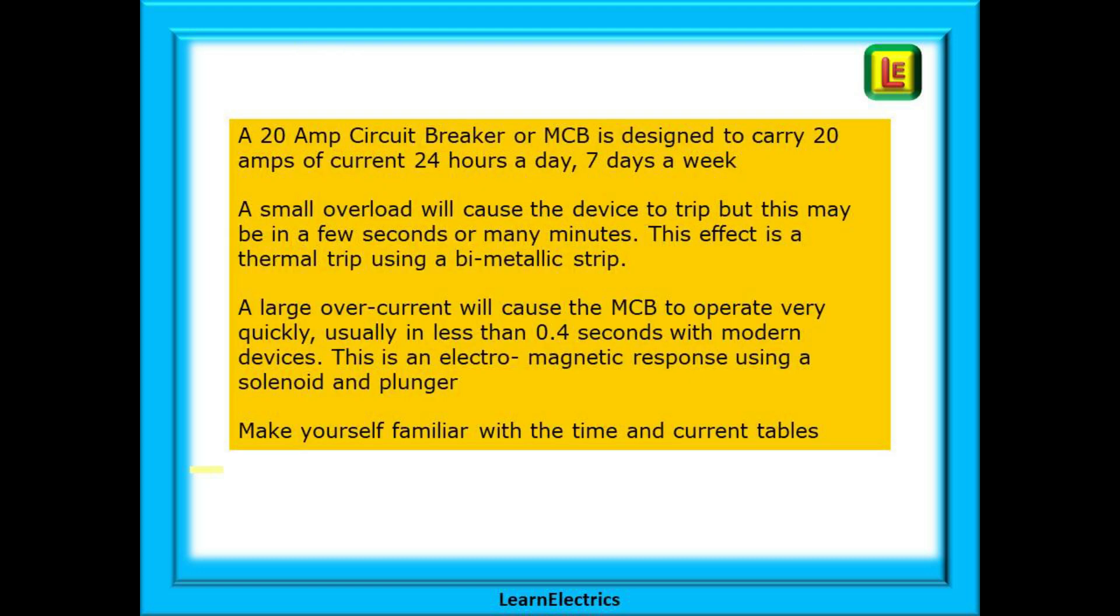Just to recap, a 20 amp circuit breaker or MCB is designed to carry 20 amps of current 24 hours a day, 7 days a week. A small overload will cause the device to trip but this may be in a few seconds or in many minutes.